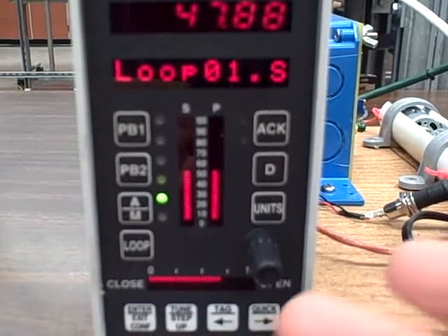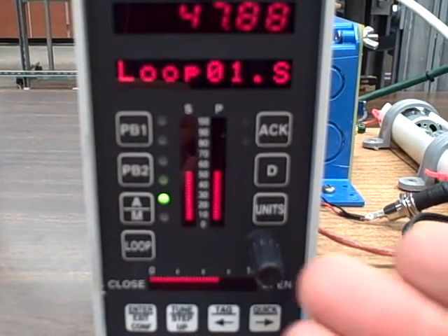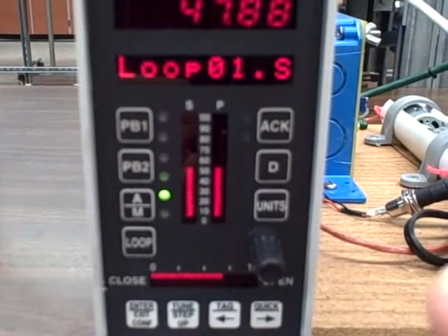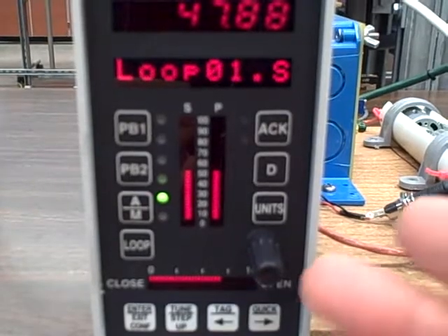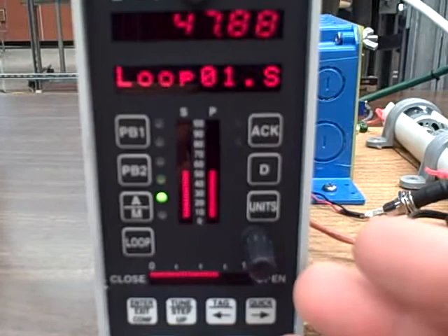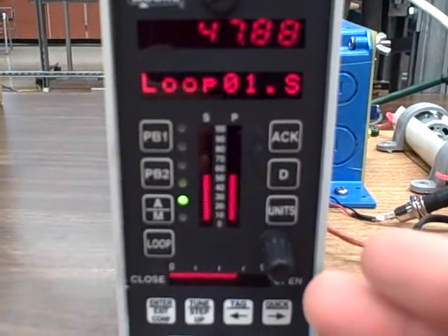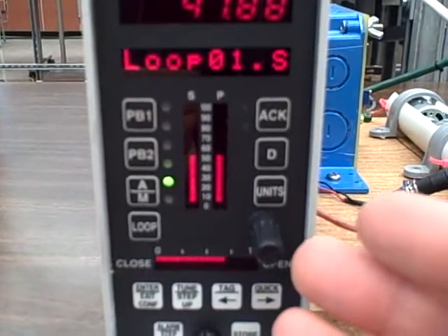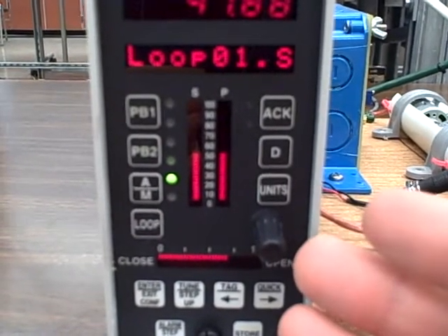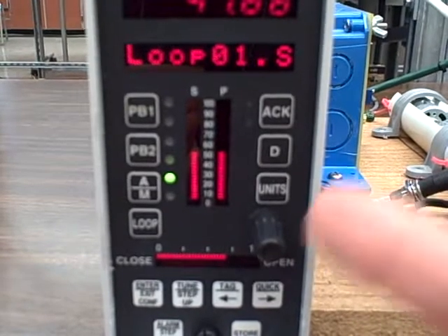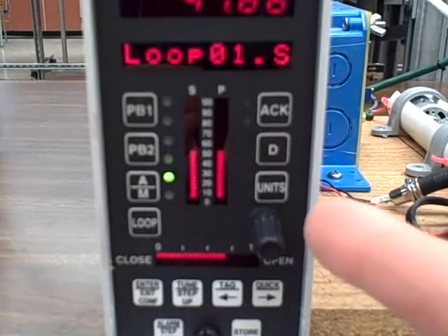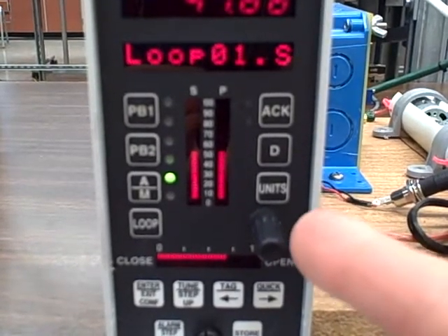So here is the problem we have with proportional only control. Too little gain, lots of offset. Too much gain, oscillation. So we try to strike a balance between those two bad effects and get something that's marginally useful or marginally practical for our loop control. The ideal solution to this, though, is to introduce a brand new element to our control algorithm, and that's called integral action. That's the letter I in PID, PID standing for proportional integral derivative. Proportional by itself has limitations. Integral helps us overcome that limitation of offset.